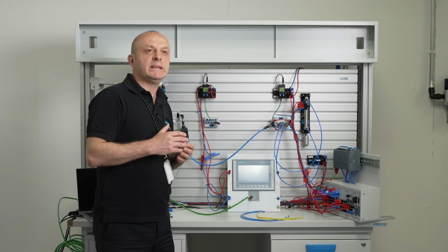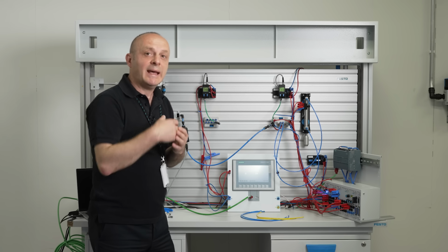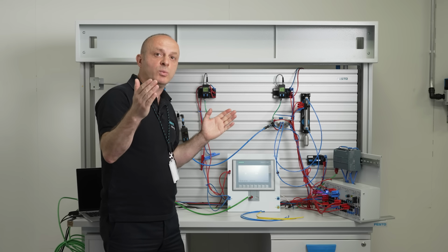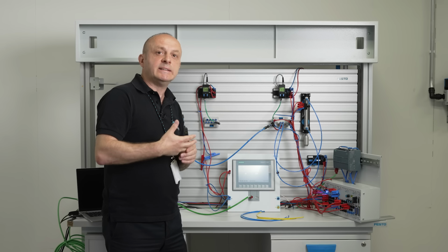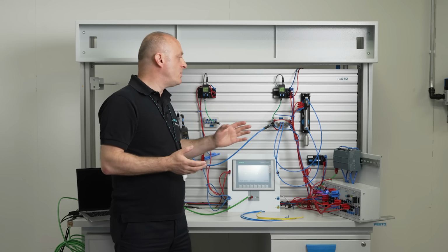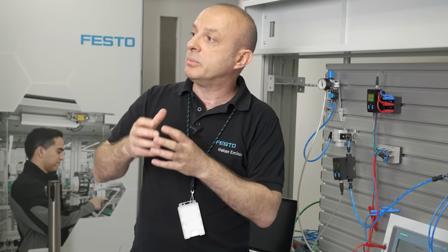We approximately increased the cycle time by a little bit more than 10%. That means on our machines, if we replace the tube with longer ones, we can create a delay. If the cycle time of the machine depends on the cycle time of this cylinder, our cycle time will be increased, so we could end up producing fewer products. You see, that's very important.